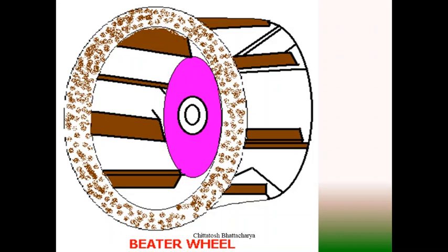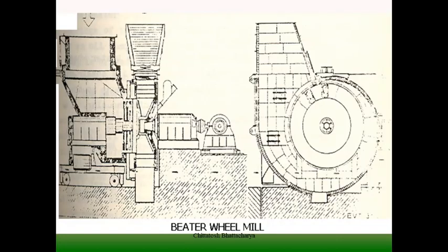Here also we have a velocity distribution arrangement, so that velocity is uniformly distributed across all the coal carrier pipes. So we have orifice nozzles, and we have one-way gate valves, so that no back pressure is developed within the milling system.